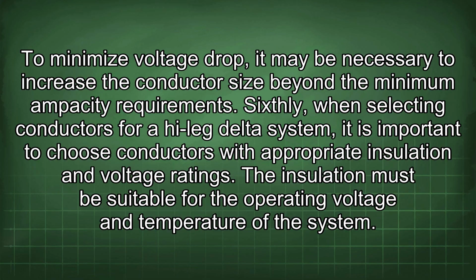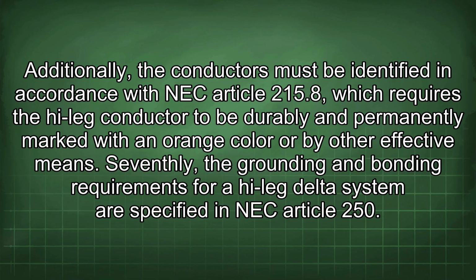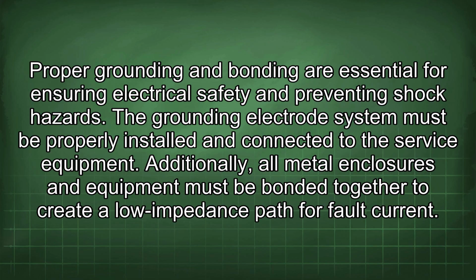Sixthly, when selecting conductors for a high-leg delta system, it is important to choose conductors with appropriate insulation and voltage ratings. The insulation must be suitable for the operating voltage and temperature of the system. Additionally, the conductors must be identified in accordance with NEC Article 215.8, which requires the high-leg conductor to be durably and permanently marked with an orange color or by other effective means. Seventhly, the grounding and bonding requirements for a high-leg delta system are specified in NEC Article 250. Proper grounding and bonding are essential for ensuring electrical safety and preventing shock hazards.